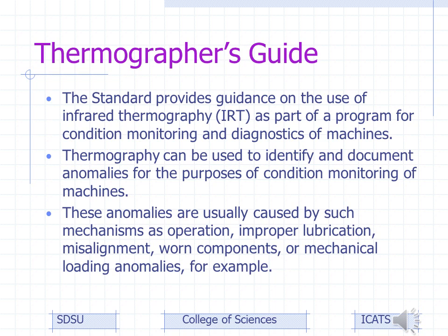It may be something as simple as tolerances that exceed the lubrication tolerance on the bearing, say the ambient temperature is too high. We've seen that. We've seen a lot of other ones. So there's very good reason for these standards and for what those standards are in particular. Lots of thought went into them.